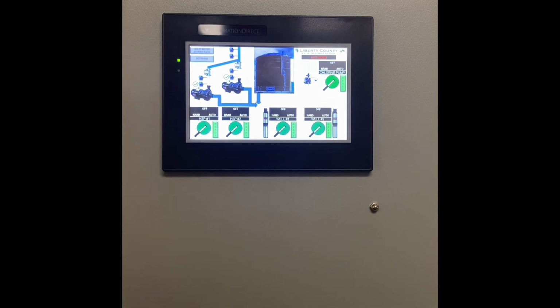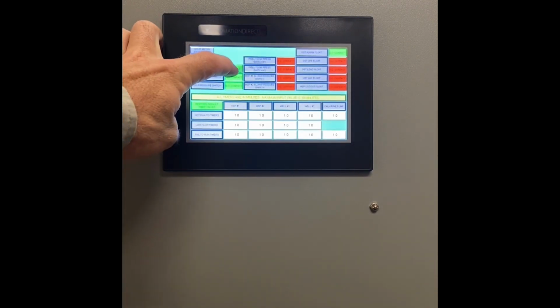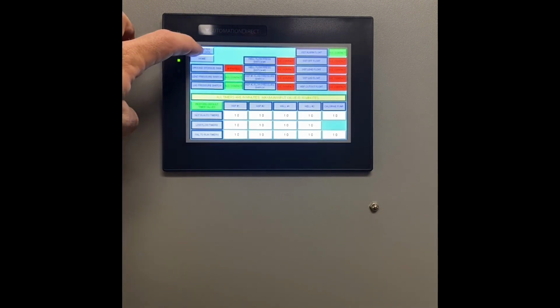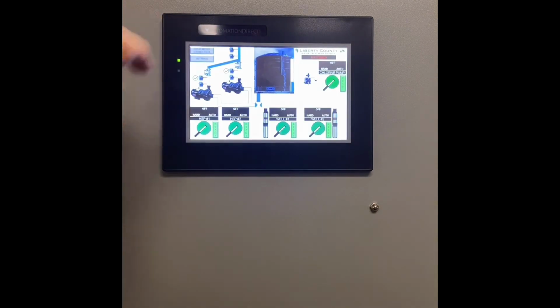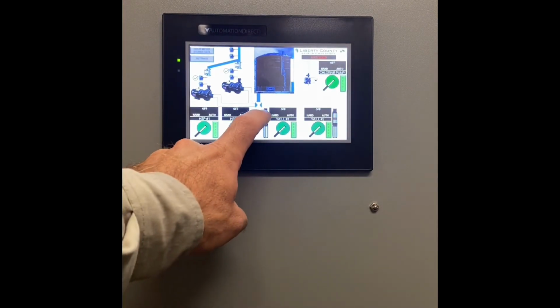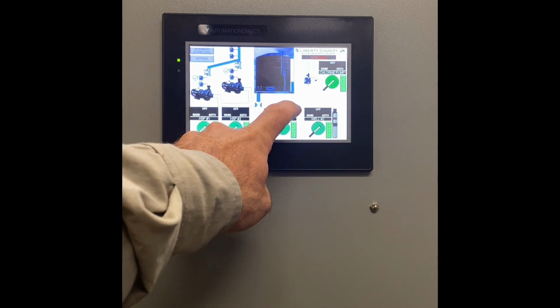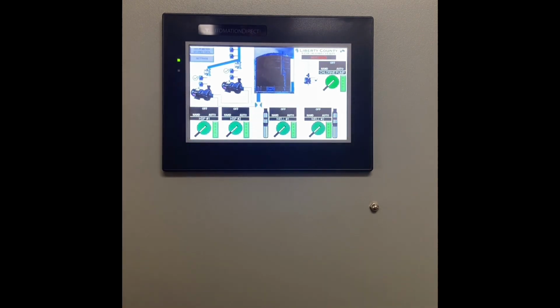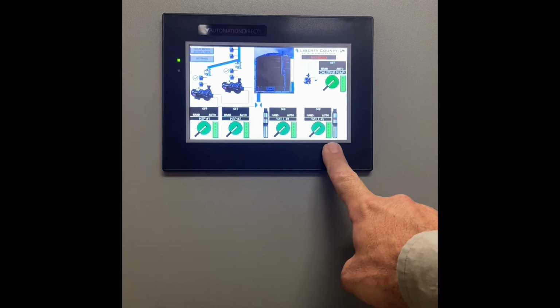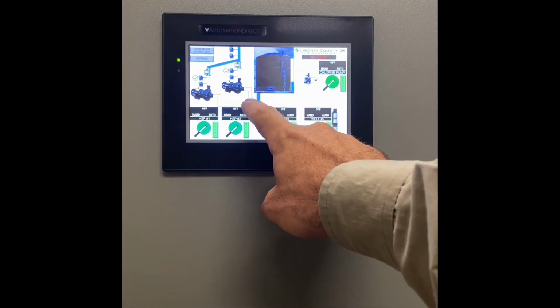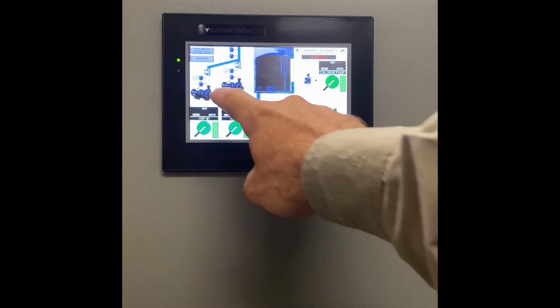Now, we will put the system in bypass. And you can see it says groundwater storage tank bypassed. And you notice that my valve has now changed position. It is now aligned to take water from the wells and deliver it right to the high service pump. You'll also notice that those pipes are an empty pipe. That is because there is not a well running at that point. Once a well begins to run, you will see blue go from that particular well, whether it's well number 1 or well number 2. It will go up to this valve, and the entire section of piping on this side will also turn blue.